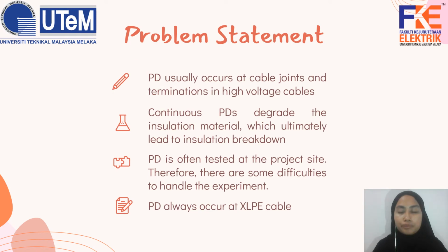So this is the problem statement of my project. First, partial discharge usually occurs at cable joints and terminations in high voltage cable. Second, continuous partial discharge degrades the insulation material, which ultimately leads to insulation breakdown. Third, partial discharge is usually experimented or tested on site, so there are some difficulties in handling the experiment. Fourth, partial discharge usually occurs in XLPE type of cable.